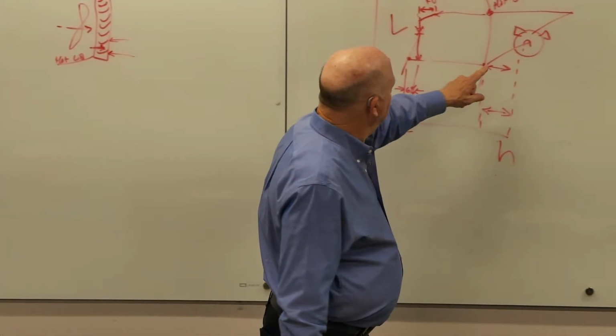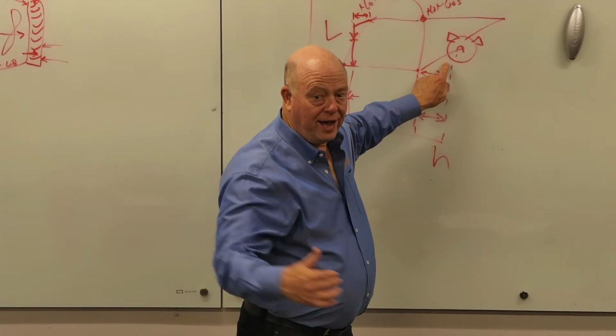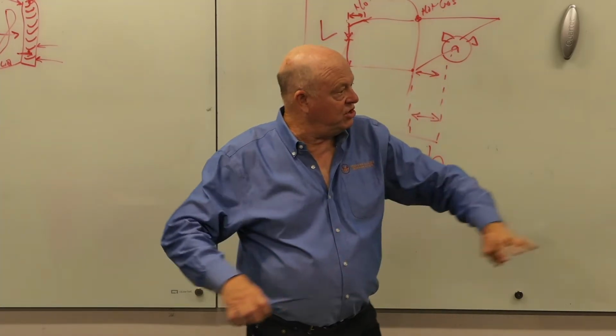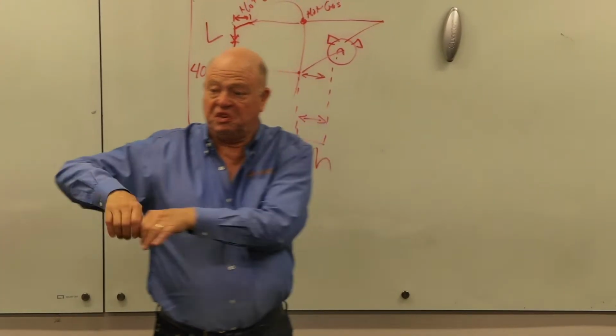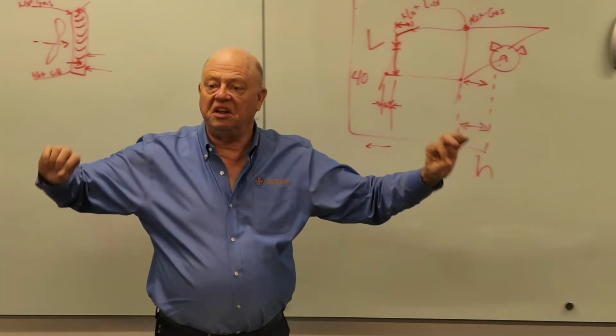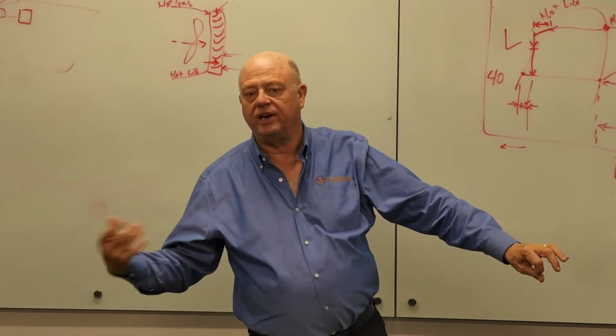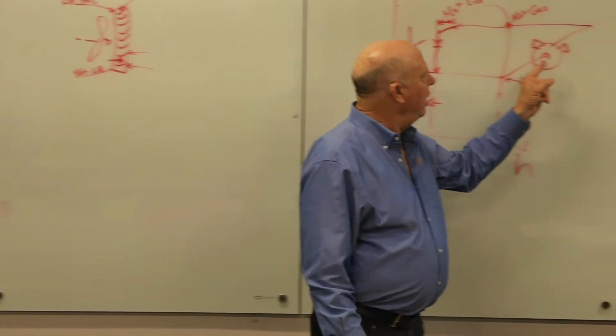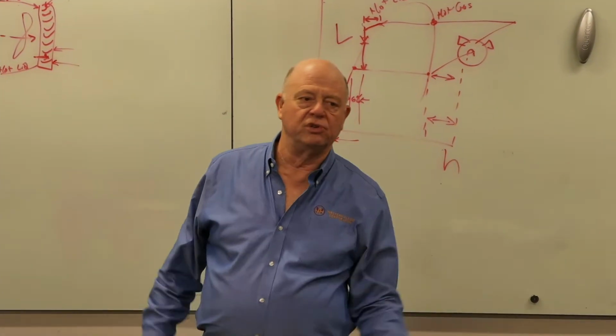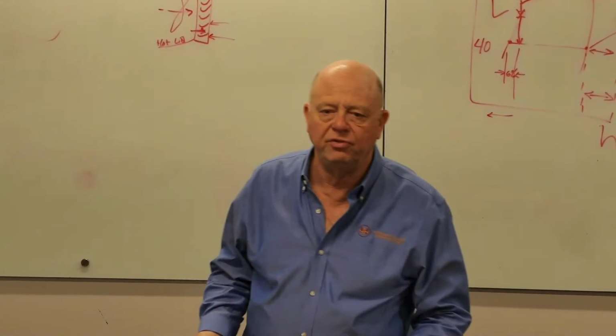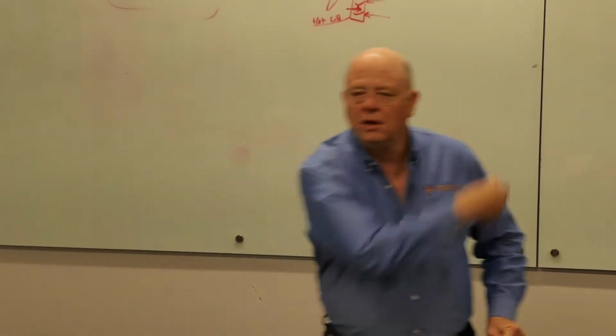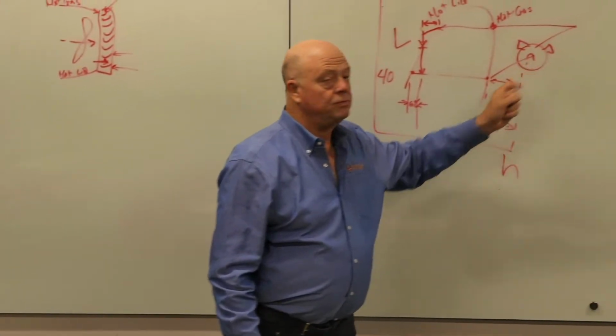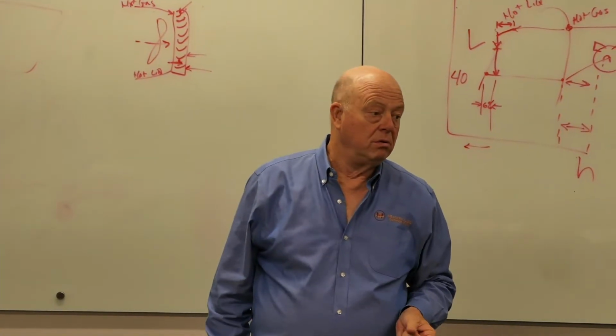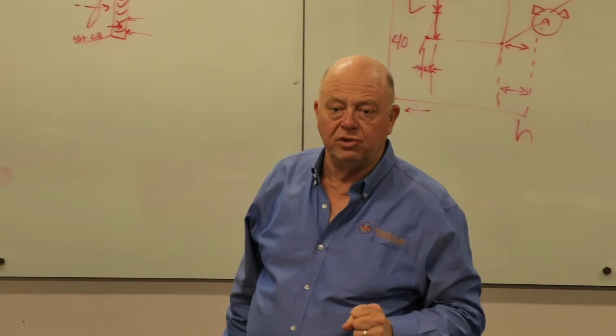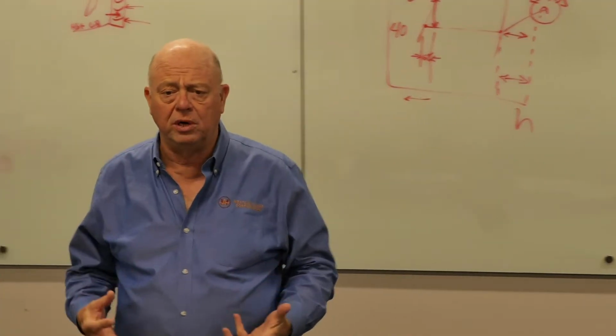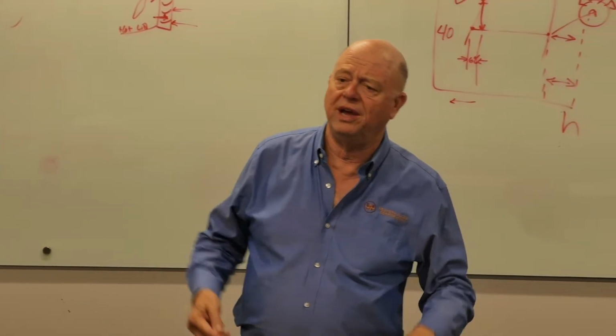And so the superheat that we had, all the gas sitting in that 80 feet of suction line condenses during the off cycle on the condensing unit, and now we slug the compressor. Slug is the term you will hear the technicians use when liquid is sucked into a compressor. And if they're just little tiny droplets, we beat up the compressor until it fails. If they're big drops, we have a sudden violent failure.